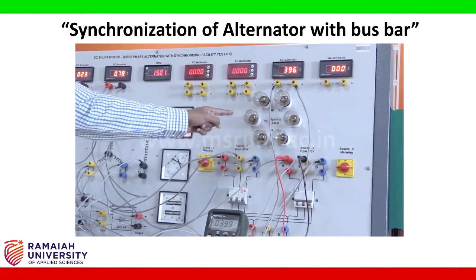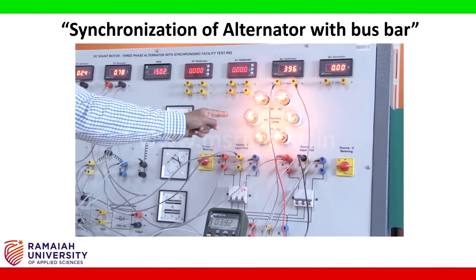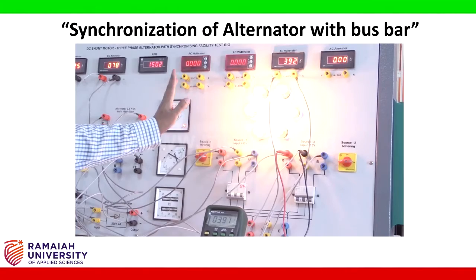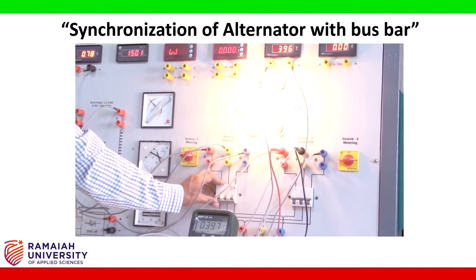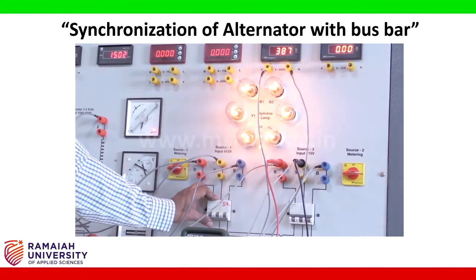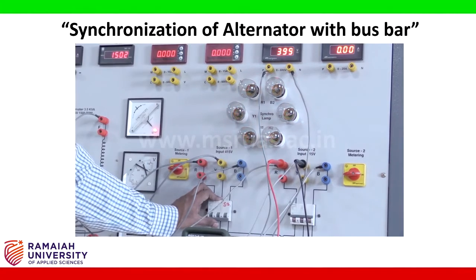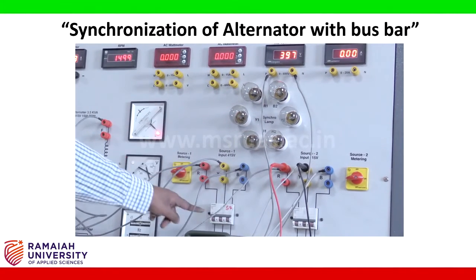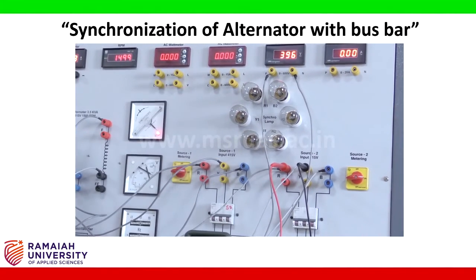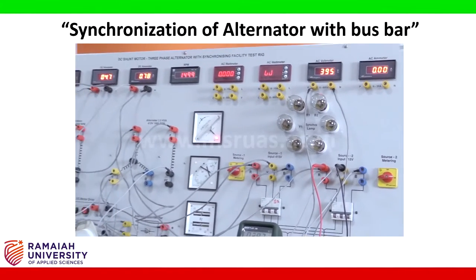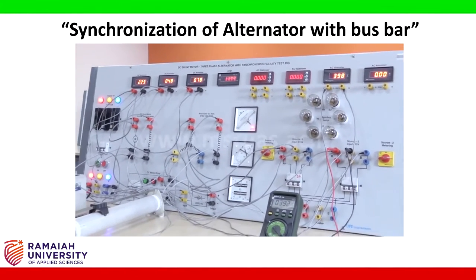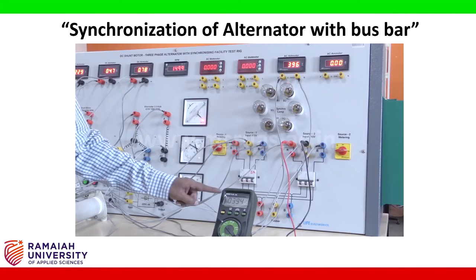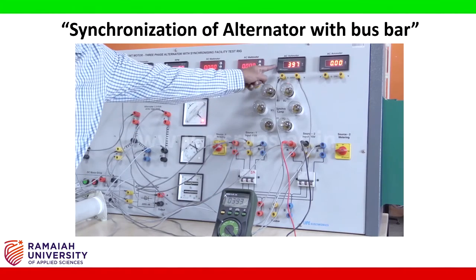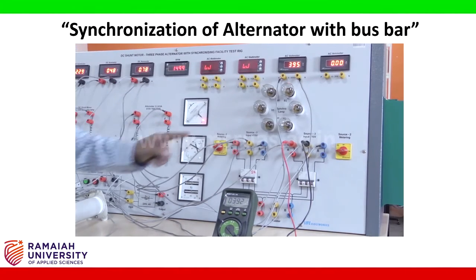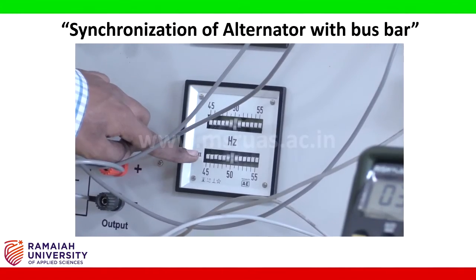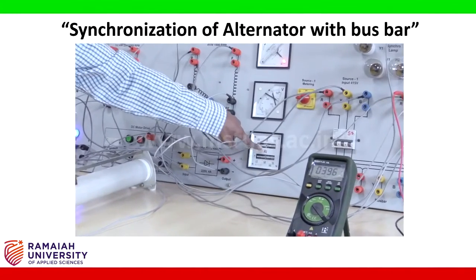Observe the turning off and turning on of the lights. When the lights go completely dark, turn on this switch. Then your alternator is perfectly synchronized with your infinite bus. Now completely dark. Now I turned on the switch. Our alternator is synchronized with the infinite bus. Now you can observe the system voltage and the alternator voltage varying together, and you can observe the system frequency and the alternator frequency are the same.